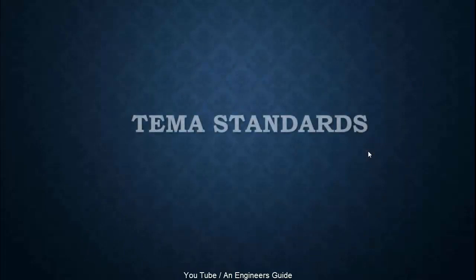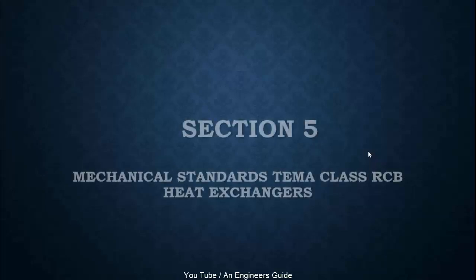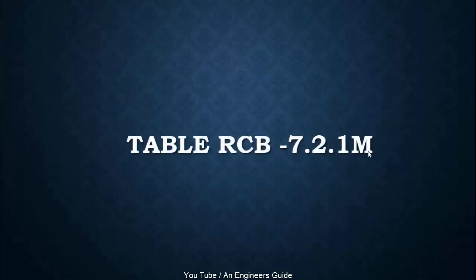For that there is an applicable standard named TEMA standard. TEMA is Tubular Exchanger Manufacturers Association. In TEMA standards you must go to Section 5, Mechanical Standards, TEMA Class R, C, B heat exchangers. Once you reach Section 5, you have to find table RCB 7.2.1M.